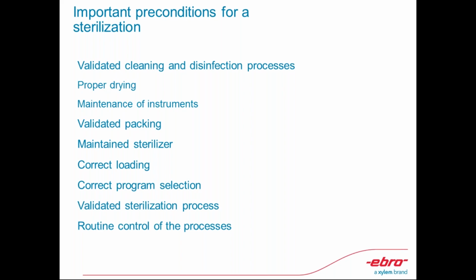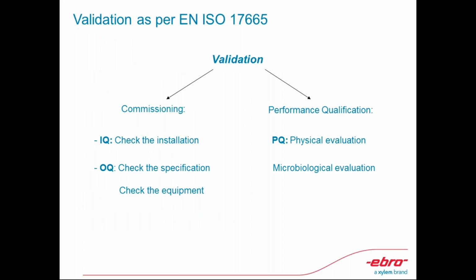You have to know this very well. A maintained sterilizer means that it should be a properly working autoclave. The correct loading, the correct program selection, and the validated sterilization processes and the routine control processes. So these are your checklist for sterilization procedures.